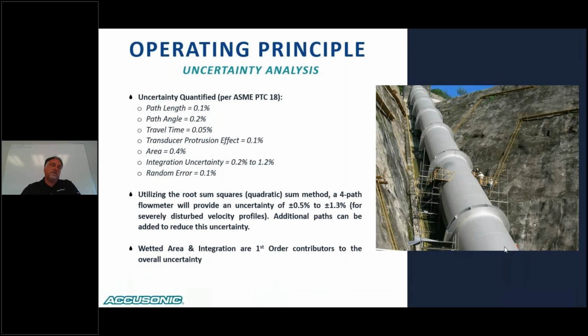And you can see that the important thing, when we're looking at all these individual values, is that the two main contributors, or the primary first order contributors, are the wetted area, and that's just because the radius or diameter is squared in the area calculation, so the actual uncertainty gets doubled. And then the integration uncertainty, and that's basically how well we are resolving those individual velocities into an average velocity.